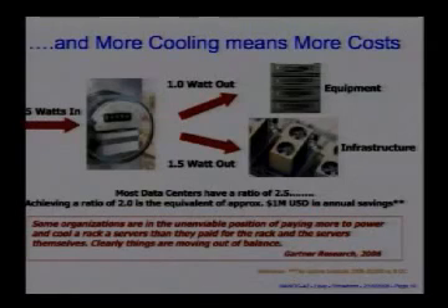I'll talk about this from a data center perspective. I operate a 750,000 square foot center in Miami. My issue is I have huge amounts of power coming in, but that power is actually dealing with my infrastructure, not necessarily going to the hardware. I think Mark showed a slide that said about 53% is going into hardware — arguable depending on the center. But the problems you have in a carrier-neutral co-location: in one cage Sprint's got a bunch of GSRs or CRS-1s. Right next door, I've got a company with 80 racks of servers blasting out heat without blanking panels, and I've got to hassle them constantly to deal with that. Next to them I've got another carrier running high density just below a dry cooler, then another carrier, then an undersea cable operator, then someone with just 2 racks in a big empty cage. How do I manage all that? It's just an absolute disaster.